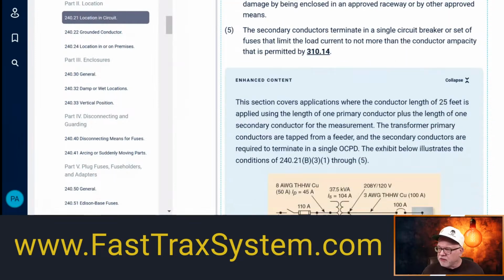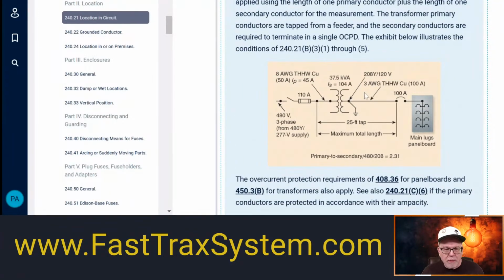Okay, so in our example, is the secondary conductor rule met by this 25-foot tap allowance? Yes, it is, because this is good for 100 amps. So it is at least sized to 84.68 amps, so it meets that rule. Now, is this bigger than that? Yes, it is. Remember, that was a minimum. In this case, it's terminating into a 100 amp device, so those secondary conductors have to be rated for the device they terminate into. They've got to be protected. So in this case, good for 100 amps. So we're good on there.